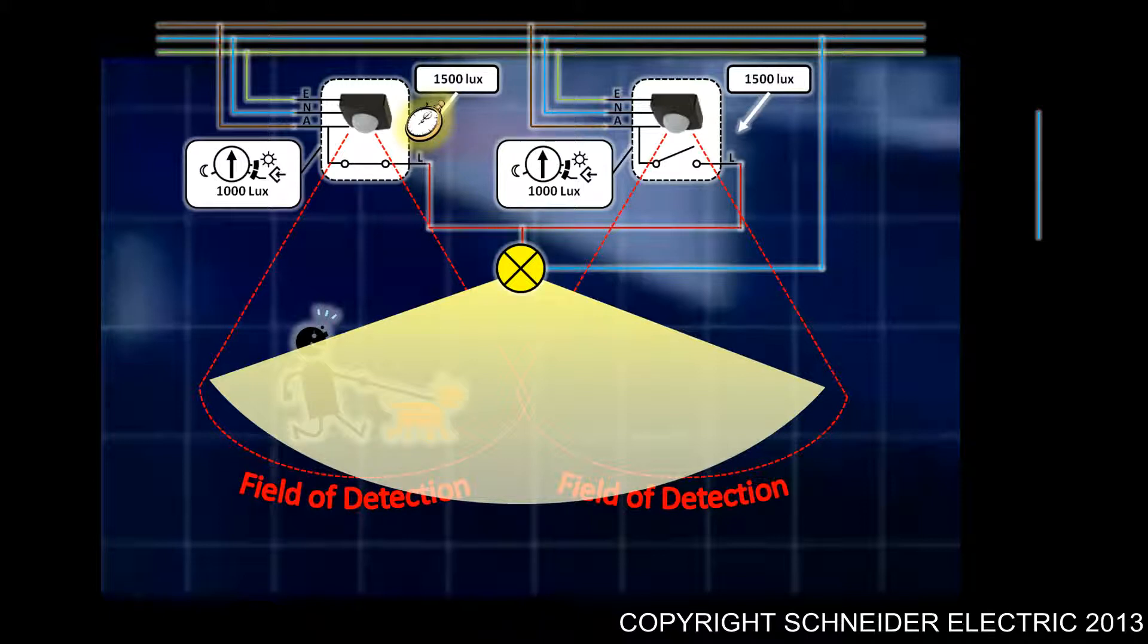Now what happens is, any movement detected by that second sensor, because it's reading, let's say for this example, with that light turned on 1500 lux, it thinks that there's sufficient light and it's going to disregard any movement. That basically means that if you walk into that second area, it's not going to be taken into consideration. That's something else just to watch out for.